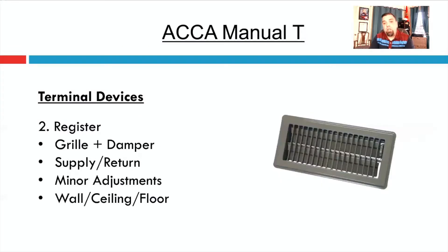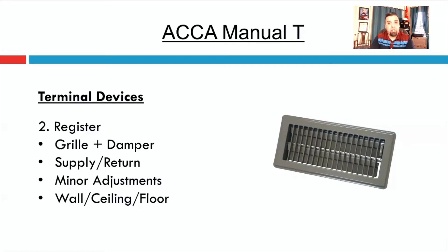A register is basically a grill plus a damper. That's the classic 421 from Hart and Cooley pictured there — grill plus a damper — it gives you the ability for minor adjustments. These could be located on the supply or the return. Most people don't use registers on the return because they don't want people shutting them off, but if you want to make minor adjustments to balancing return ducts you could. Keep in mind the more you close that damper, the noisier it gets because velocity goes up to pull the same volume of air. Most people put dampers in ducts for large adjustments; minor adjustments can be done with the damper in a register. You'll typically find registers on walls, ceilings, or floors.